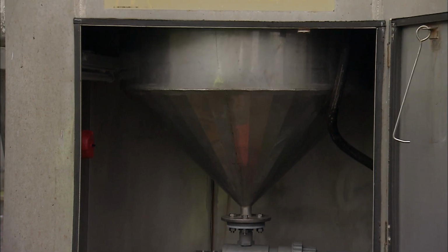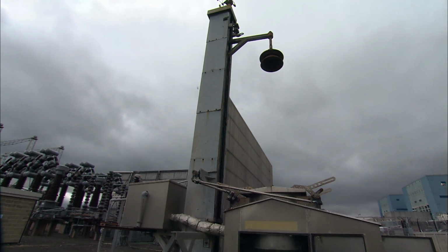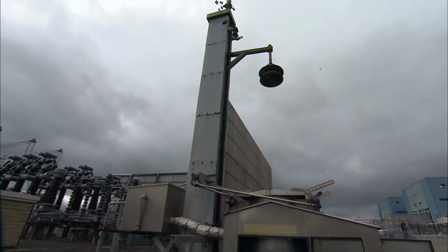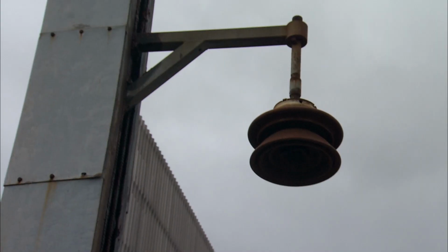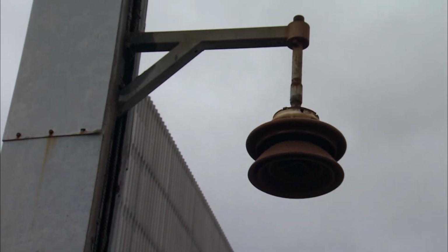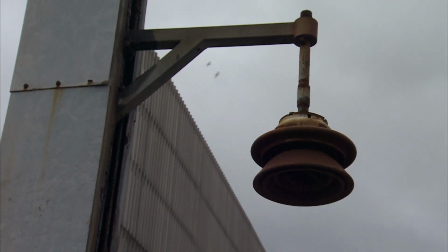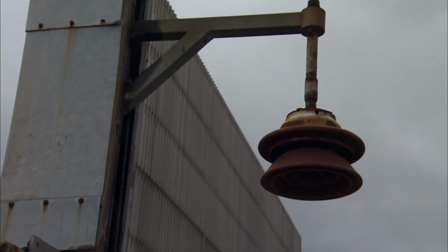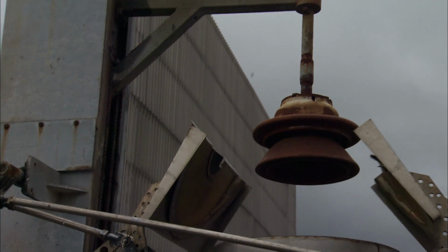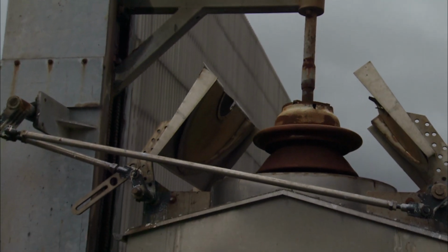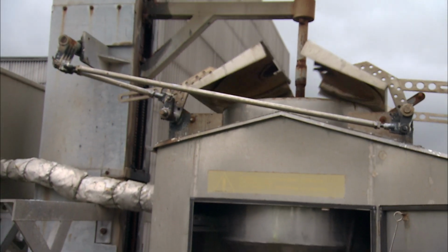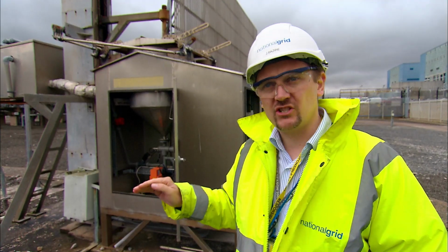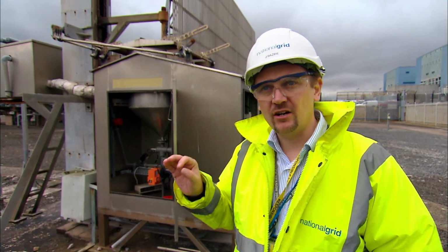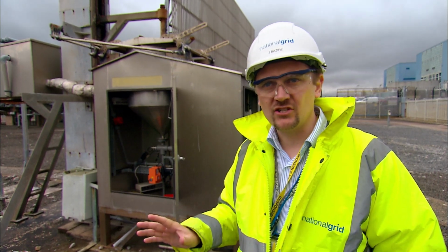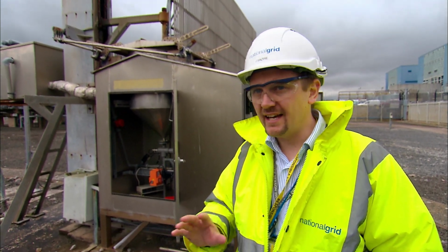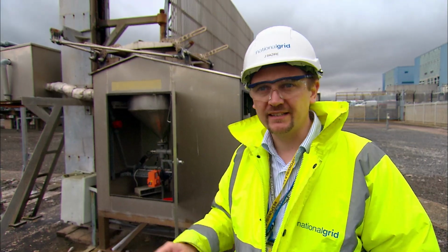At the heart of the system is an automatic pollution monitor. A section of insulator has been hanging in the salty wind. Now it's going to be tested. This is one of 2 pollution detectors. This is known as the west zone pollution detector. The other one's on the east side of the substation. This is picking up the deposits of salt that are blown across from the channel. Once it reaches a certain level, it will initiate a wash. There's no manual intervention, it's all done automatically, any time of the day, any day of the week.